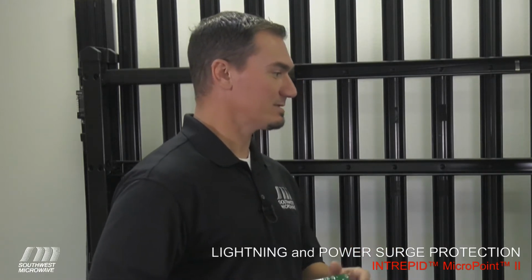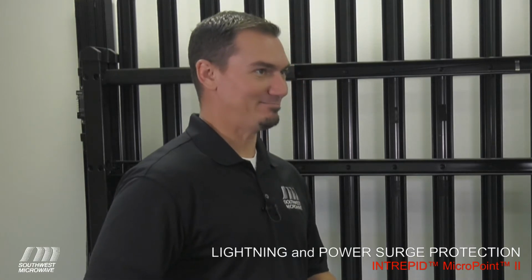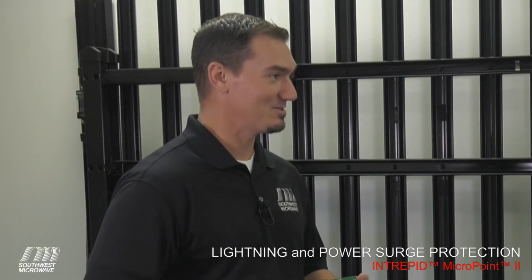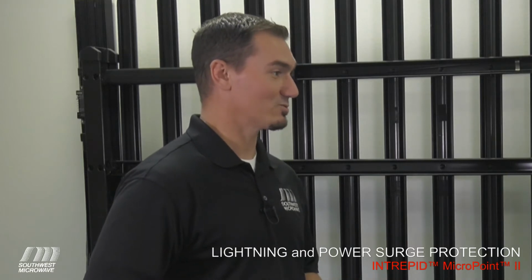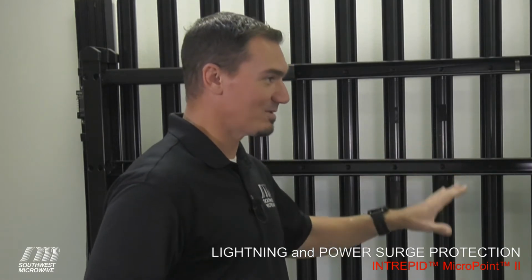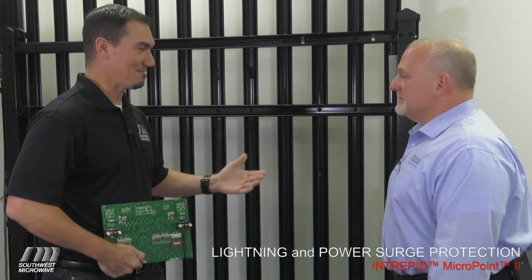Most of the sites that will be using CCTV systems, gate controllers, and other electronic devices around the perimeter know that those are going to be susceptible to EMI, RFI issues, lightning damage, and ground surge, and most of those sites take appropriate precautions right off the bat. The first precaution is grounding the fence. Quality fences that are installed at these sites will be grounded appropriately, and there is a recommendation to ground at multiple points along the perimeter, so it is actually grounded. And that's the first step.